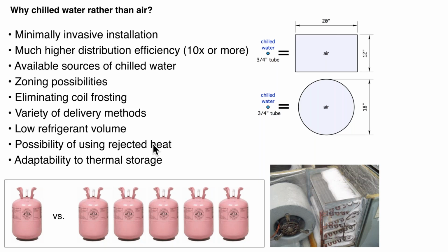There are some applications where, when we provide or produce chilled water, the heat of rejection can be useful. We've designed systems over the years that provide chilled water for one purpose and also recover the heat from the condenser of the chiller and use that for a different purpose. One example, we did a project for a facility that manufactured gelatin. If you've ever made gelatin, you know you need chilled fluid or chilled water and ice to do it. So we're providing the chilled water with a water-to-water heat pump, and then we're recovering the heat on the condenser side and using that for domestic hot water in the building. So those are some really nice synergistic applications.